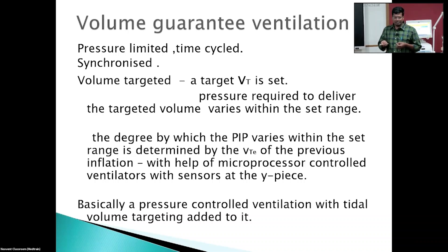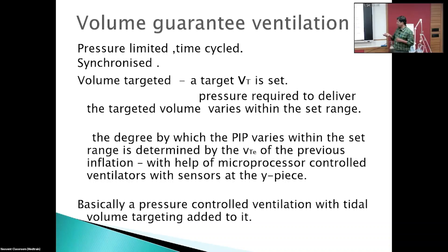In simple pressure-controlled ventilation, within the set Ti and synchronization, we achieve a tidal volume delivered to the baby. We are not actually controlling that tidal volume based on changes in lung mechanics. Here, we target a tidal volume set on the ventilator, and the peak inspiratory pressure moves up and down depending on the change in lung mechanics to deliver the target tidal volume. The degree by which the PIP varies is determined by the exhaled tidal volume of the previous breath.